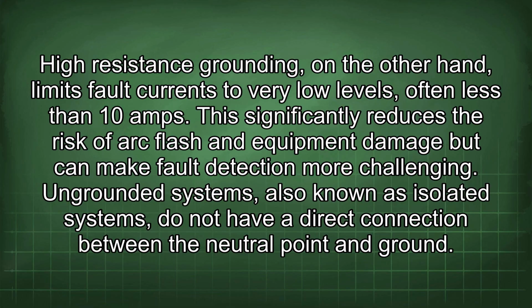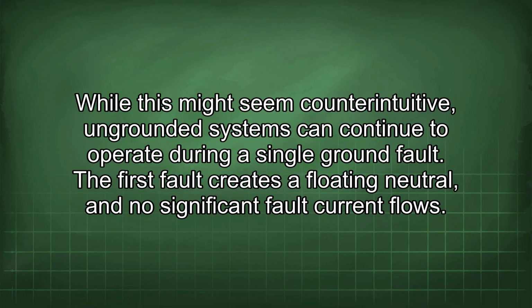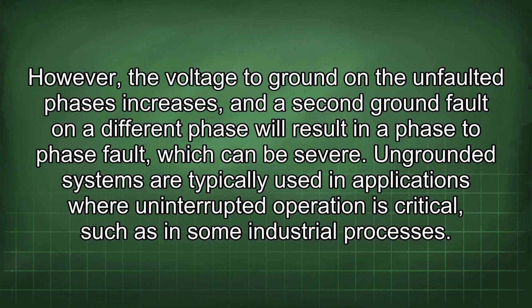Ungrounded systems, also known as isolated systems, do not have a direct connection between the neutral point and ground. While this might seem counterintuitive, ungrounded systems can continue to operate during a single ground fault. The first fault creates a floating neutral and no significant fault current flows. However, the voltage to ground on the unfaulted phases increases, and a second ground fault on a different phase will result in a phase-to-phase fault, which can be severe. Ungrounded systems are typically used in applications where uninterrupted operation is critical, such as in some industrial processes.